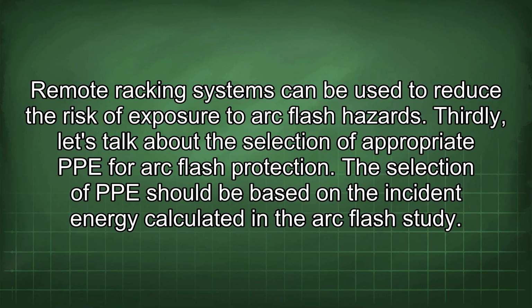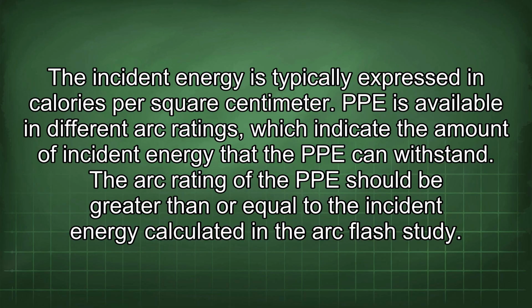Thirdly, let's talk about the selection of appropriate PPE for arc flash protection. The selection of PPE should be based on the incident energy calculated in the arc flash study. The incident energy is typically expressed in calories per square centimeter. PPE is available in different arc ratings, which indicate the amount of incident energy that the PPE can withstand. The arc rating of the PPE should be greater than or equal to the incident energy calculated in the arc flash study.